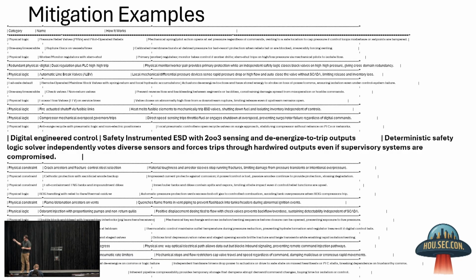Even if the solution in the controller is as simple as an if-then or if-else check—like if this flow rate is less than 100 CFM—that simple check could be moved to a physical logic check using a flow switch or some mechanism to help control the consequence or provide that boundary check, so that even if the controller was compromised through maintenance or some activity, I still have a physical apparatus that provides a material science check coordinated with that logical check.